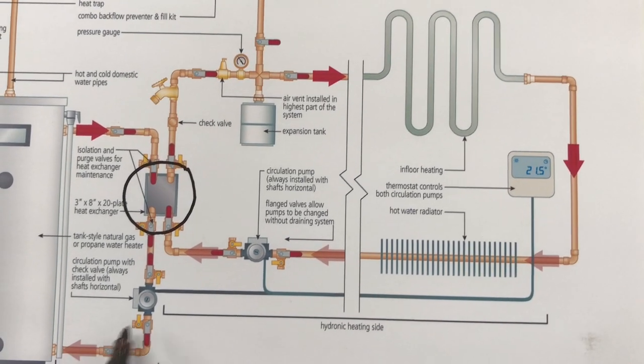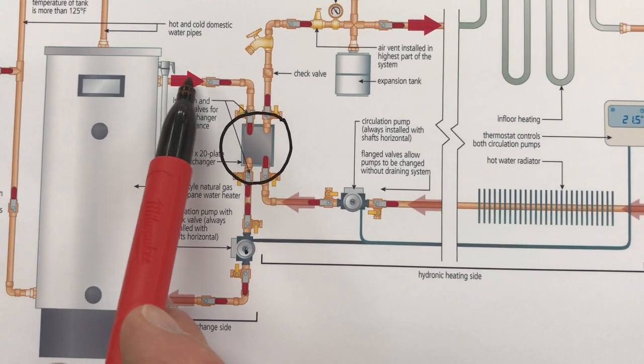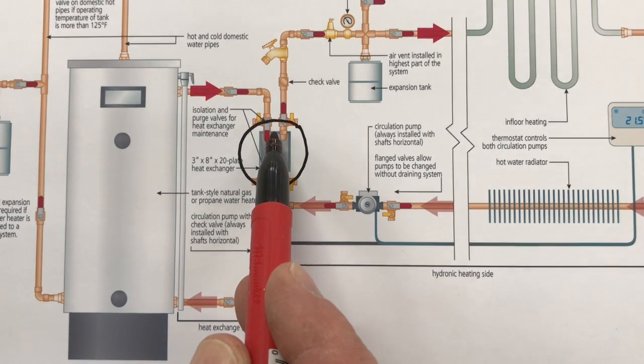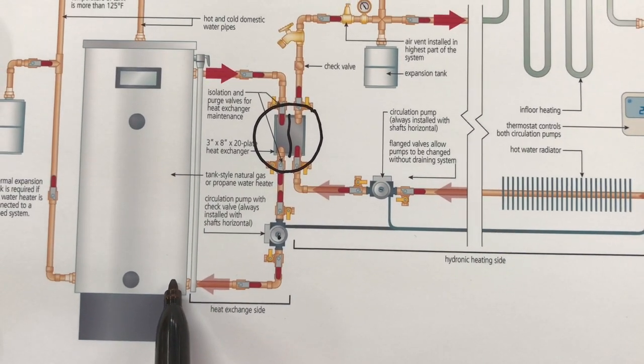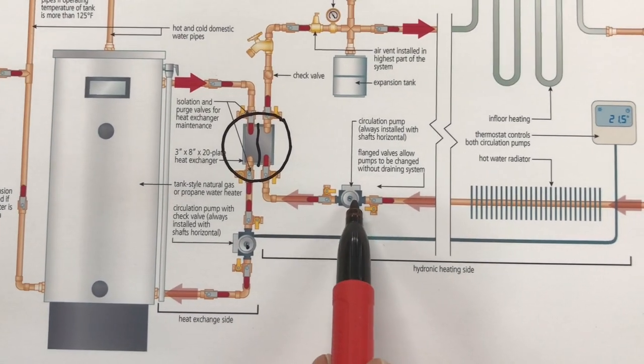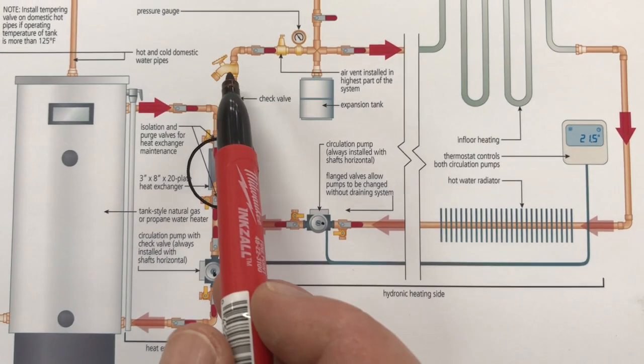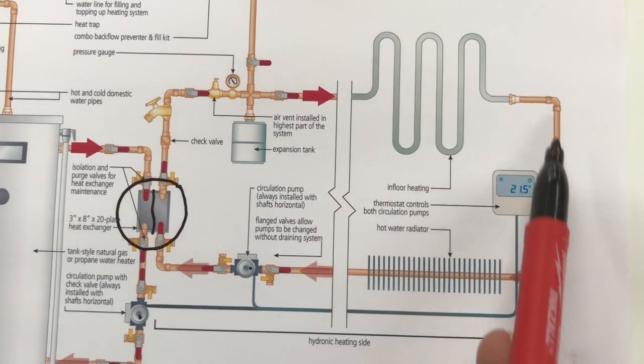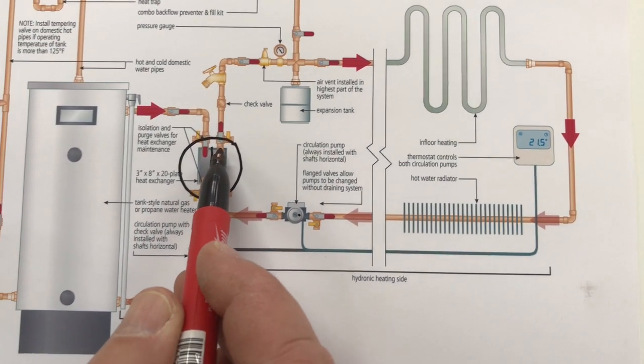It triggers the circulator pump here which circulates the hot water off the top of the tank down through the one side of this heat exchanger and then back into the tank at the bottom. Now the second circulator pump is also triggered and it circulates the hydronic heating water through the house, back through and on the other side of the heat exchanger.